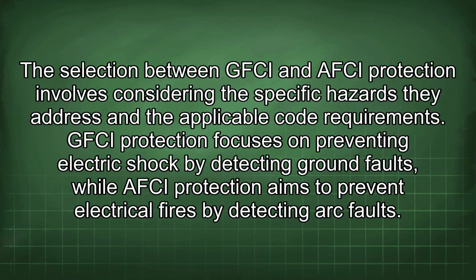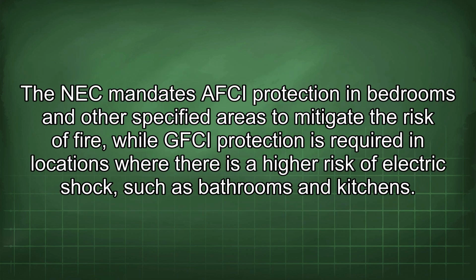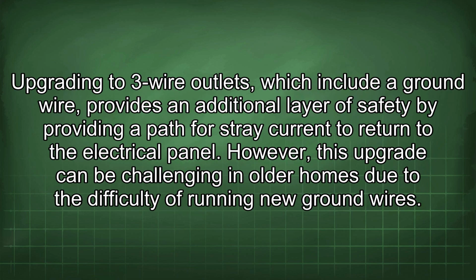The selection between GFCI and AFCI protection involves considering the specific hazards they address and the applicable code requirement. GFCI protection focuses on preventing electric shock by detecting ground faults, while AFCI protection aims to prevent electrical fires by detecting arc faults. The NEC mandates AFCI protection in bedrooms and other specified areas to mitigate the risk of fire, while GFCI protection is required in locations where there is a higher risk of electric shock, such as bathrooms and kitchens. Upgrading to 3-wire outlets, which include a ground wire, provides an additional layer of safety by providing a path for stray current to return to the electrical panel.